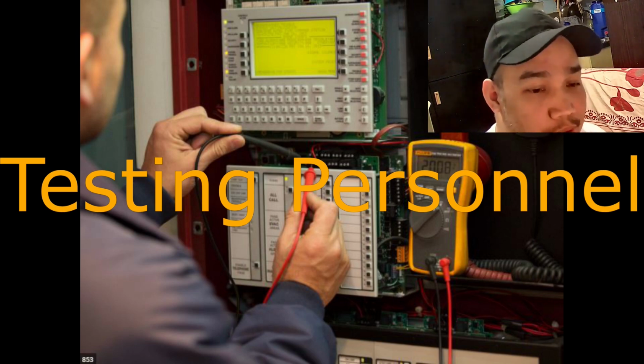Lesson learned: since it really affected the operation of the plant, I was screwed for failed communication, lack of planning and experience. This is why personnel with knowledge and qualification and enough experience are required for testing the complete fire alarm system, including its interface.